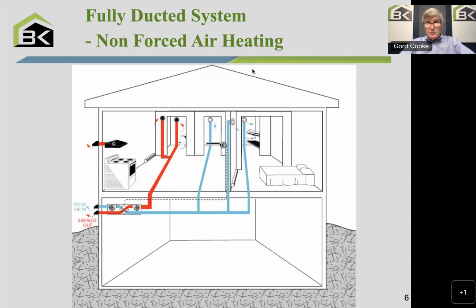The second type of installation is for when you don't have a central forced air system. Let's say it's electric baseboard. Sometimes houses are wood-heated, wood stove houses. In this case, the exhaust is still being pulled from the bathroom and the kitchen, but now you'll see the blue ducts delivering air directly, and ideally you would deliver it to bedrooms and main living areas. In fact, the codes would say at least 1 fresh air duct to each bedroom and at least 1 to a main living area. So here's a 2-bedroom house, which ends up with 3 ducts, 1 to each bedroom, 1 to the main living area. Fairly straightforward installation.